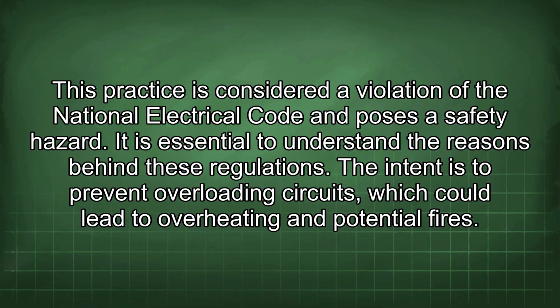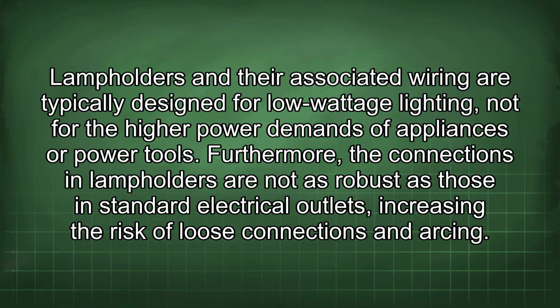It is essential to understand the reasons behind these regulations. The intent is to prevent overloading circuits, which could lead to overheating and potential fires. Lampholders and their associated wiring are typically designed for low wattage lighting, not for the higher power demands of appliances or power tools. Furthermore, the connections in lampholders are not as robust as those in standard electrical outlets, increasing the risk of loose connections and arcing.